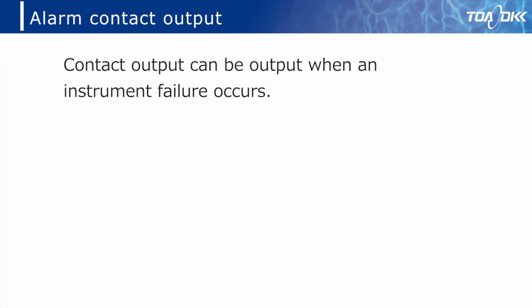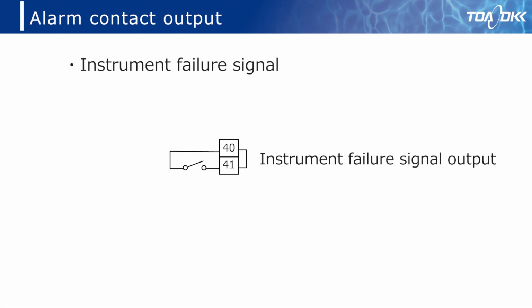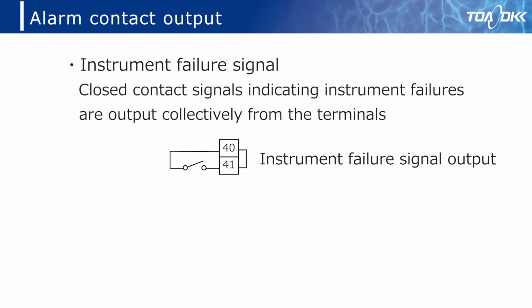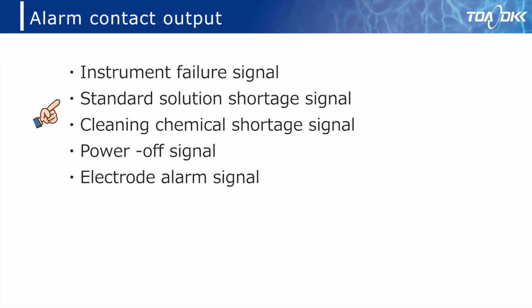The alarm contact output can output a contact output when an instrument failure occurs. This section describes the instrument failure signal. A closed contact signal is output when the instrument is in a fault condition, such as when calibration cannot be performed. As the closed contact signals are output collectively, it is necessary to check the type of error. There are also a standard solution shortage signal, cleaning liquid shortage signal, and power-off signal. These signals are output immediately after the fault occurs.